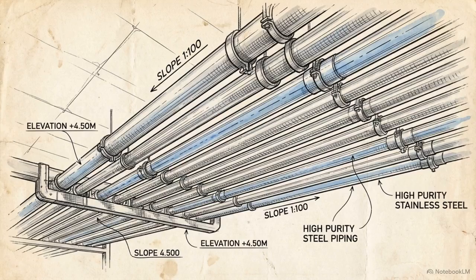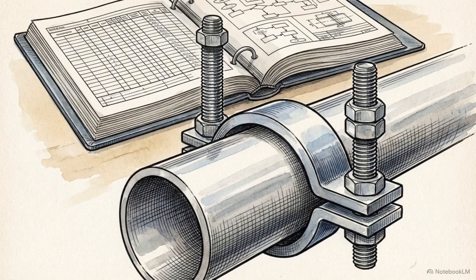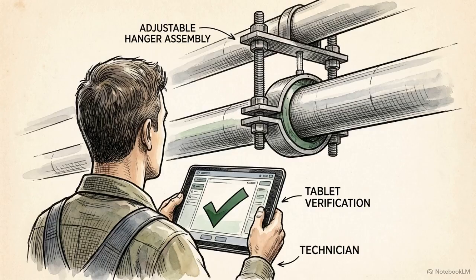Following these steps results in a system with a precise 1/8 inch per foot pitch, secured by adjustable hangers, and backed by a complete data package. To maintain this state, include hanger integrity and slope checks in your annual preventative maintenance schedules.